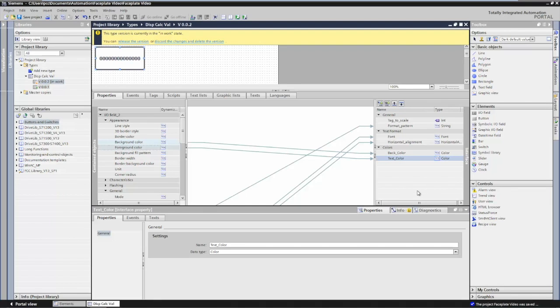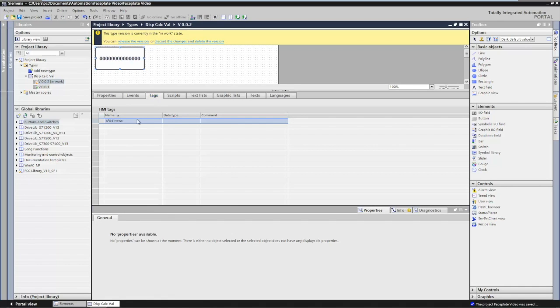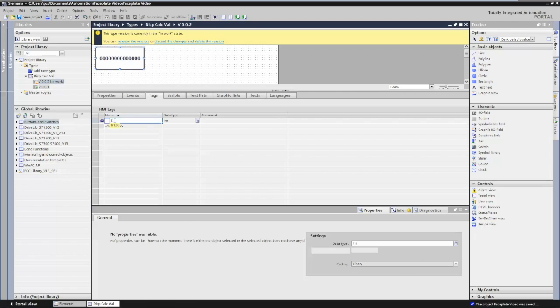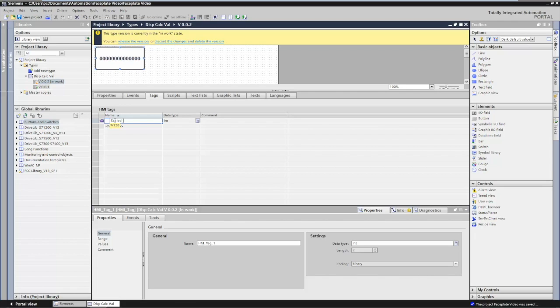So now I have the properties created for my faceplate. The next thing I'm going to do is create a faceplate tag. I'll go to the tags tab and create a tag called scale_value. The data type I'll make a real data type — I'm going to store the result of my calculation. A faceplate tag is only known within the faceplate.